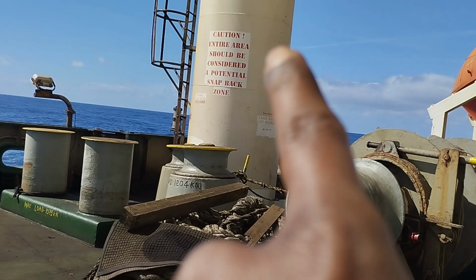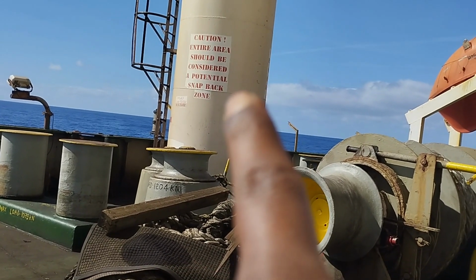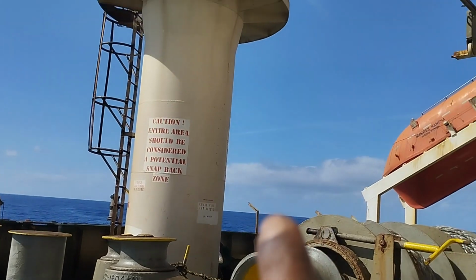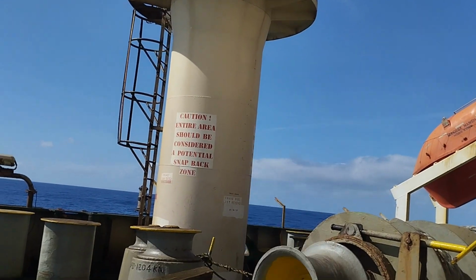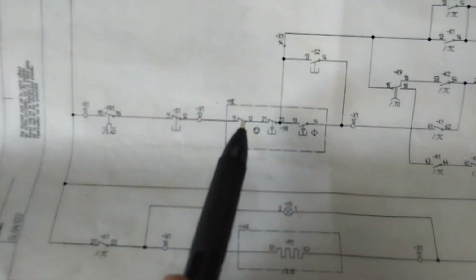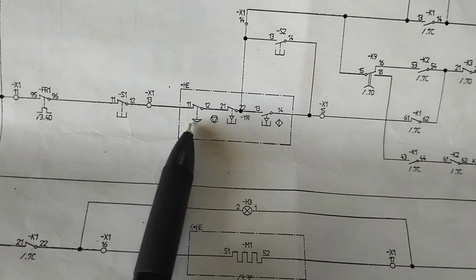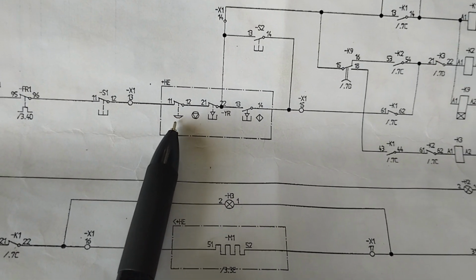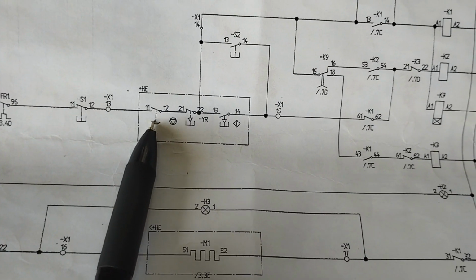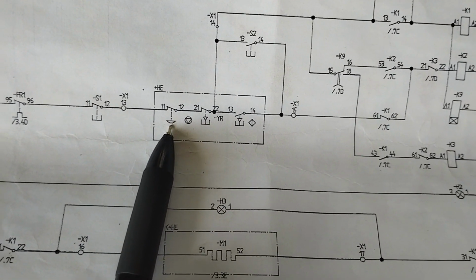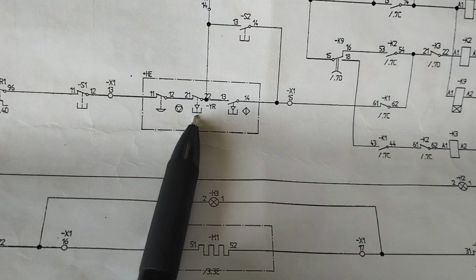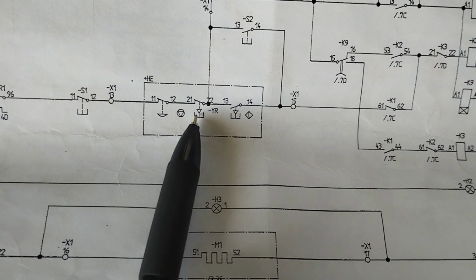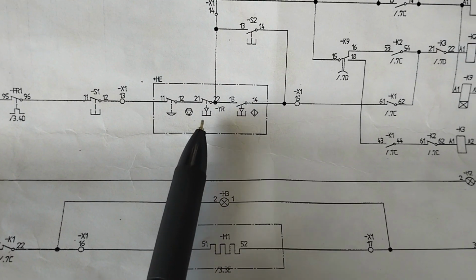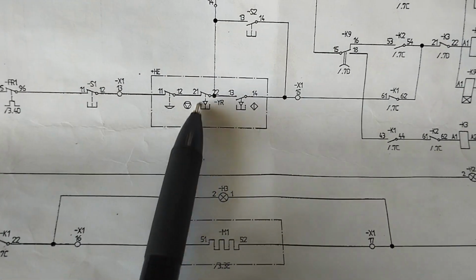Basically this is inside. Okay, you can see the caution: entire area, consider the potential snap back zone. Inside this crane post, this box is there. So what is written in this box? You can see, very careful, this is very important. This is the emergency stop. In case of emergency you can stop this crane at any time at a local position. This is the oil level. Okay, so this is very important. This is the electro-hydraulic crane. If the oil level is low, you cannot start this crane.